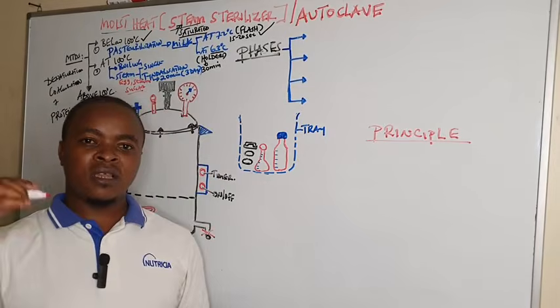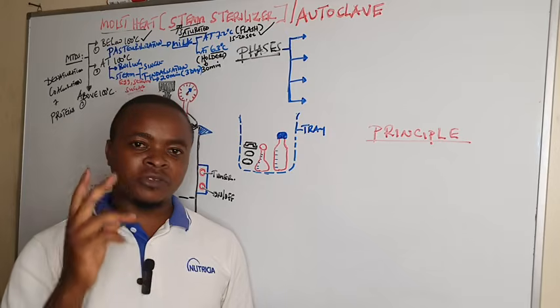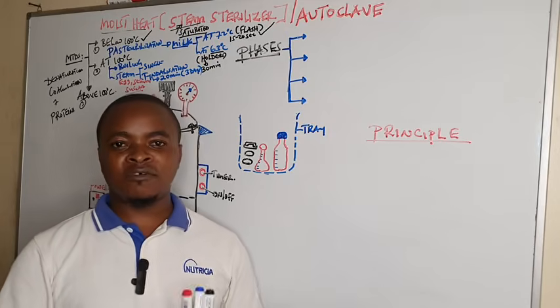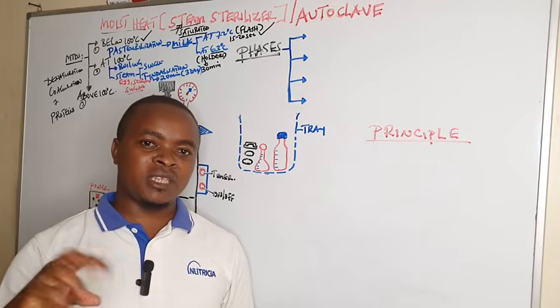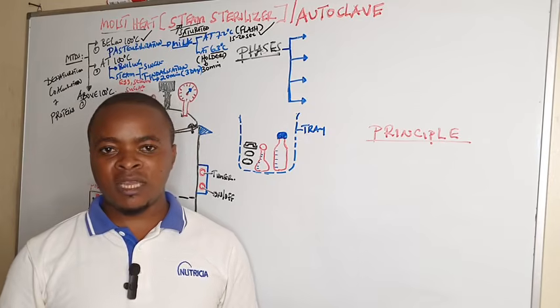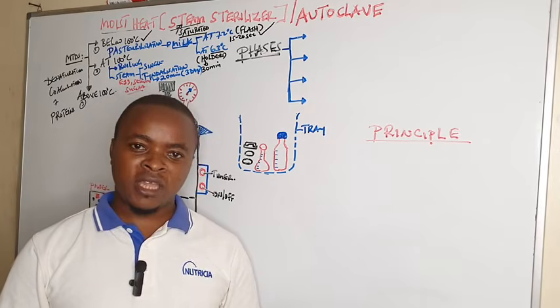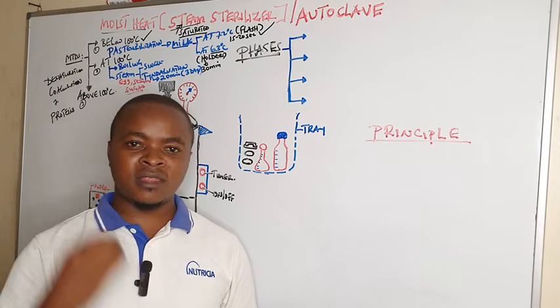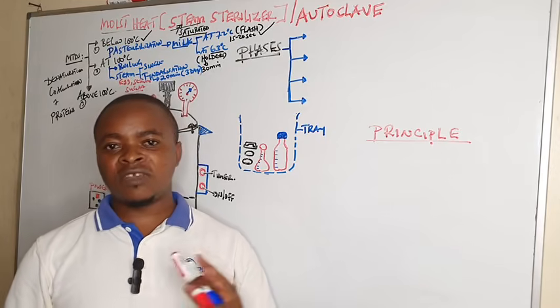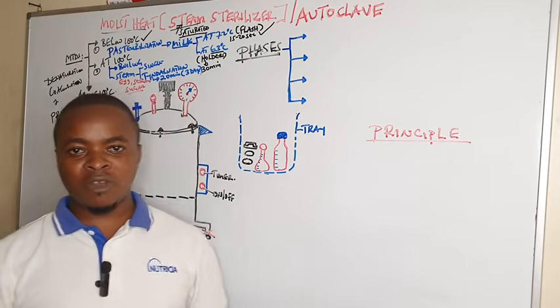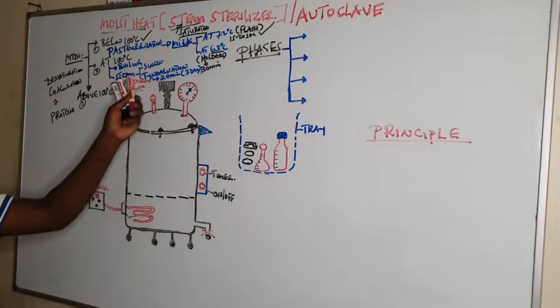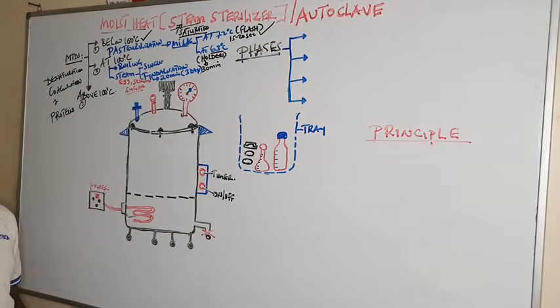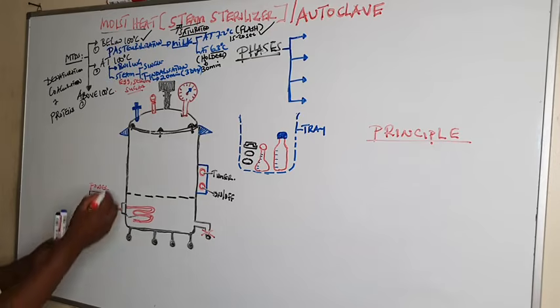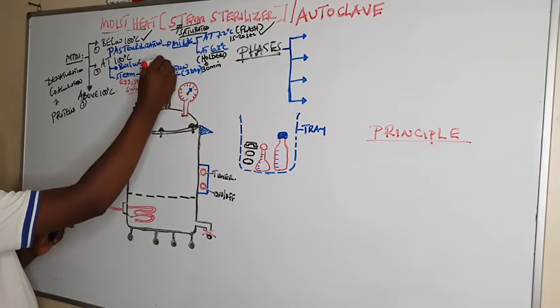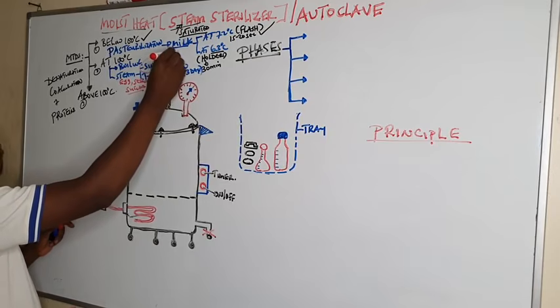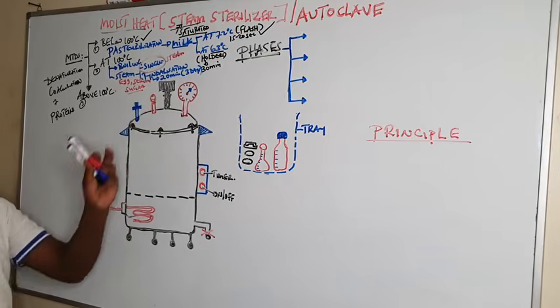That is 20 minutes at 100 degrees using steam for 3 consecutive days, whereby the first day is for killing vegetative forms, then we keep it to allow the spore forms to germinate, then the second day we expose, we again keep it to allow the spore forms to germinate, then by the third day we have killed both the vegetative and spore forms of all kinds of microorganisms. With tyndallization, we can maximize and get what we call 100% sterilization, which is different from single exposure, whereby you expose substances to steam at 100 degrees. So the preferred is tyndallization.